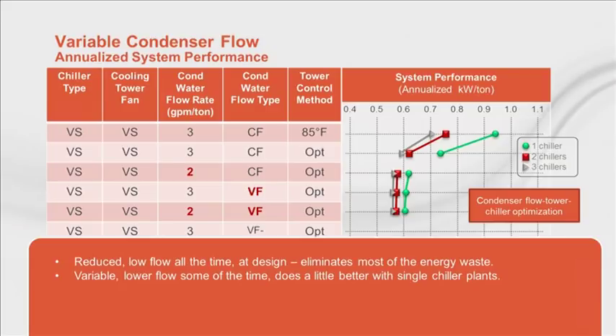Reducing the condenser design flow rate, but not varying the flow, achieves high performance without increasing control complexity. The design team can choose a lower flow rate and simpler controls, or a higher flow rate and increased complexity. The results are similar. On existing plants, you might not have both options. If you aren't able to get a new chiller, one that's capable of low flow and a slightly elevated condensing temperature, you must control variably to low flow, but only some of the time.